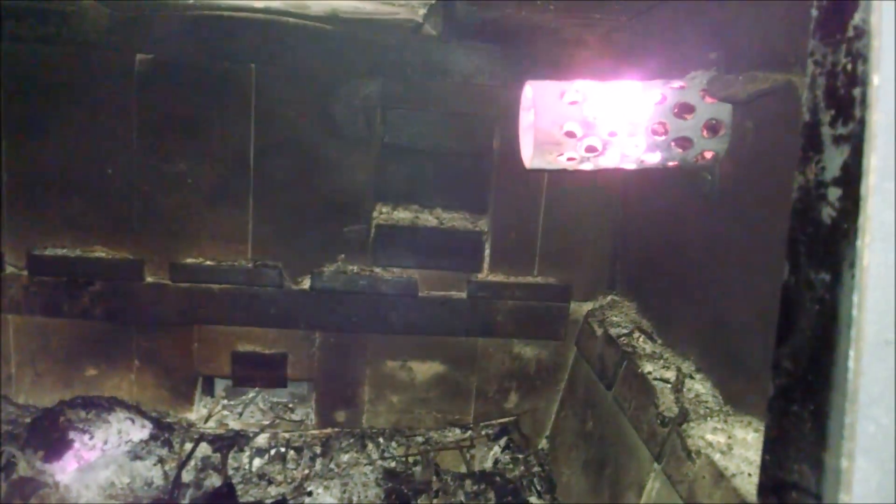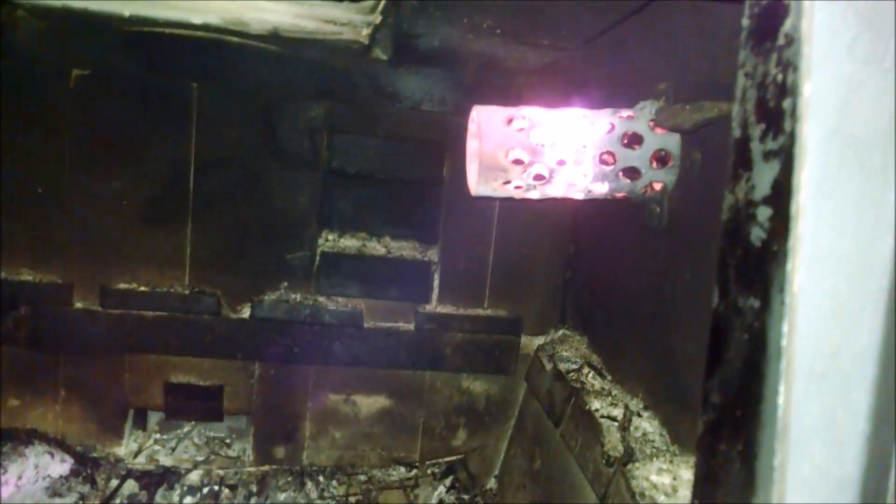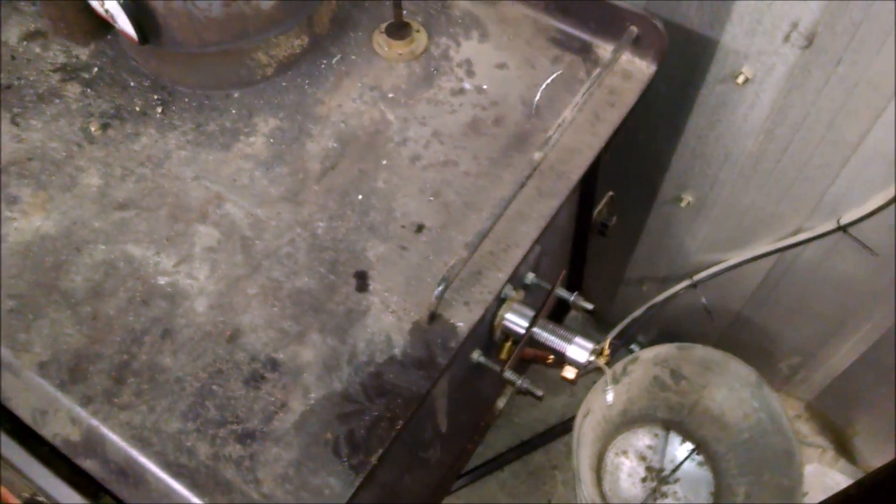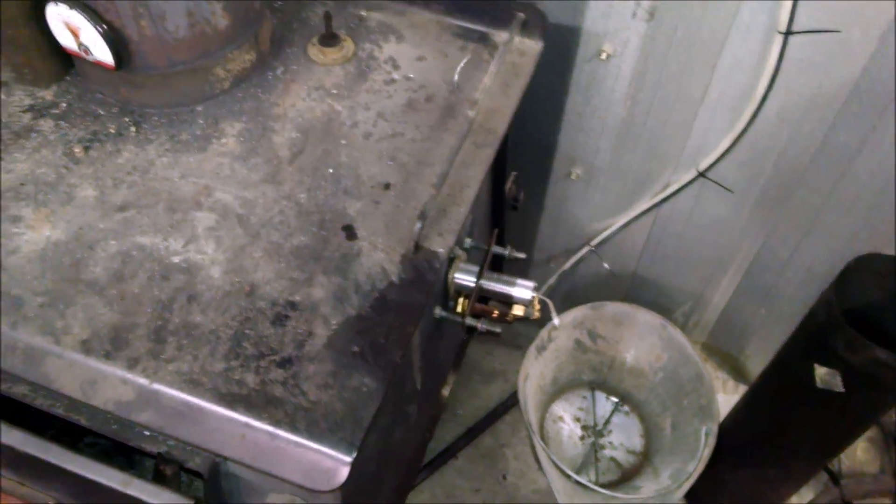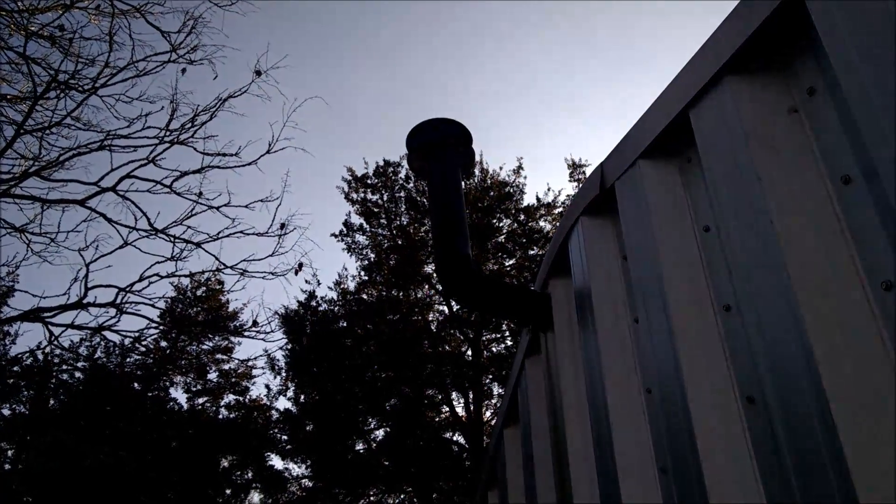But we'll go ahead and stop it. So hit stop. And you can see it almost immediately goes out. And it does get quite hot. A lot of that's the slag from the oil residue. But some of the housing itself is actually glowing as well. The big thing is that once you do shut it down, you want to continue to let it have some air. I better go ahead and shut this off. You want the air to help cool the nozzle down. This stove can get rather hot. And it can cook that nozzle and the o-ring and everything else if you just shut off the air right away. So usually running in the air for about 15 minutes after the stove was shut off is good enough to take care of that.